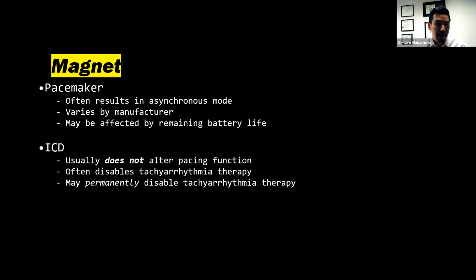So let's get into the detail about what a magnet does. For a pacemaker, a magnet often results in asynchronous mode, but it varies by manufacturer—this is the scary part—and it can be affected by remaining battery life. For an ICD, it actually does not usually alter the pacing function; it often disables tachyarrhythmia therapy. One cautionary tale is that it may permanently disable tachyarrhythmia therapy, so you've got to be cognizant of that too.